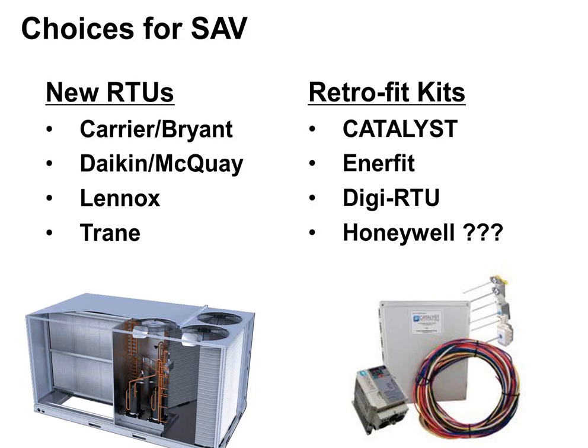There are 3 manufacturers, like we said earlier, that make retrofit kits to do this, and that's one way to do it. However, the other thing I've been doing lately is I've been using standard off-the-shelf Honeywell parts to do this, to the point now where we got the Honeywell guys looking at making it into a kit of their own. So it's pretty easy to do that. If you want help using Honeywell controls to retrofit it on an existing rooftop, you can do that.